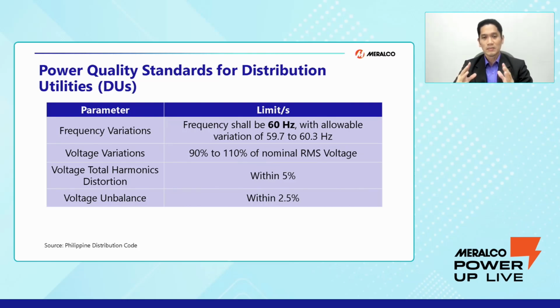All of that, Meralco as a utility should be able to maintain the voltage between 90 and 110% at the connection point. For the voltage total harmonic distortion, it is within 5% as per the PDC, as well as the total demand distortion or TDD. And for the voltage unbalance, it is within 2.5%.